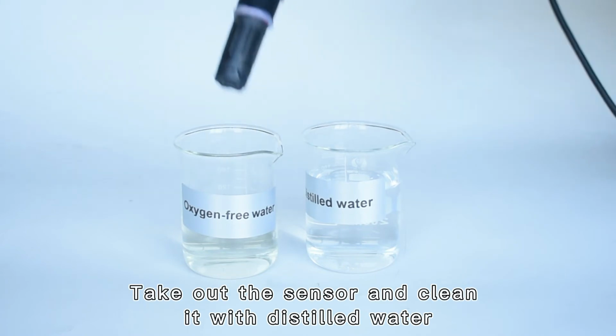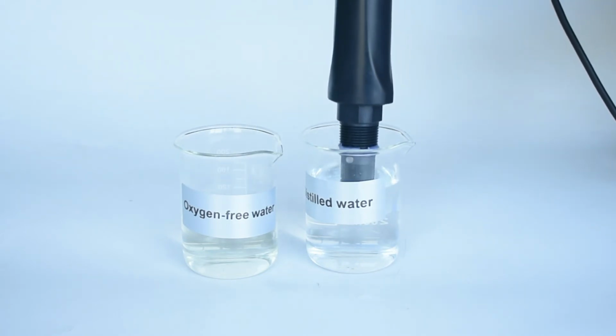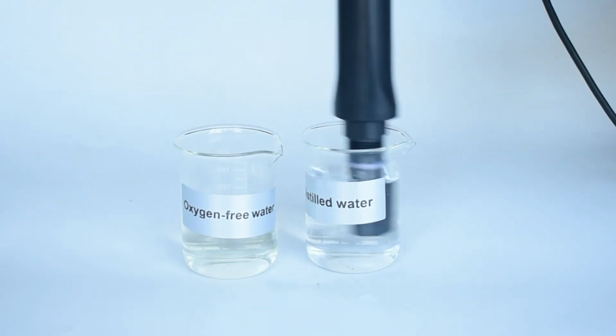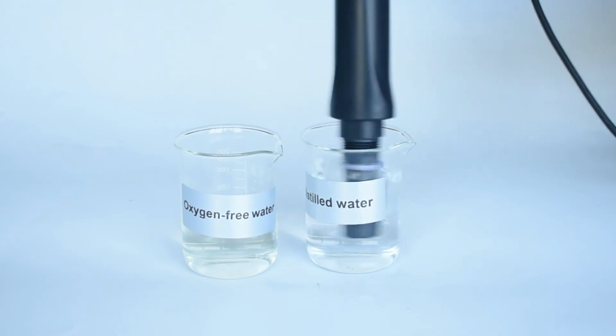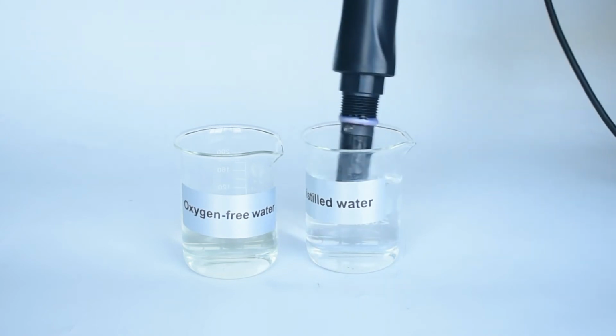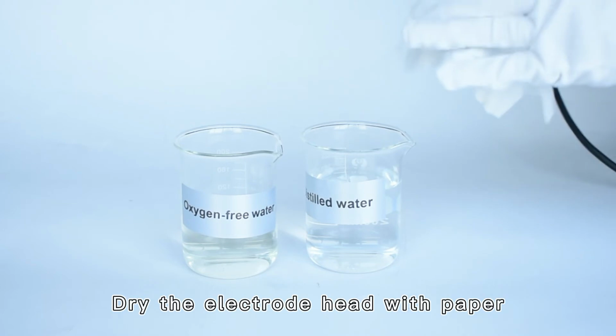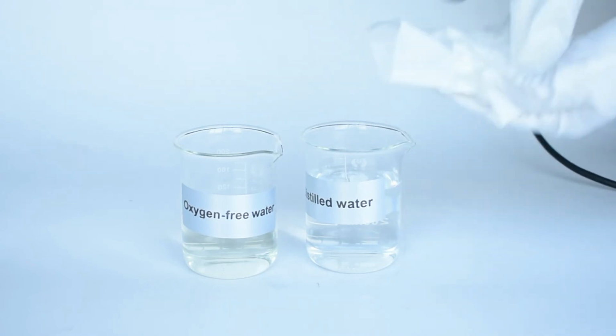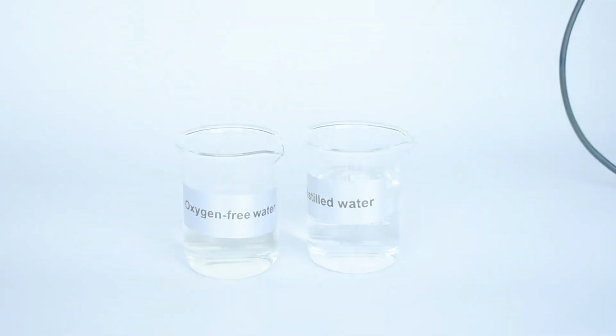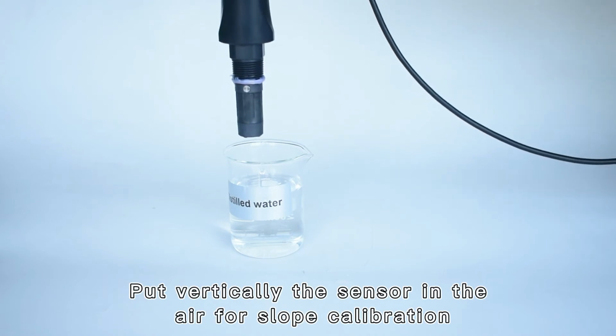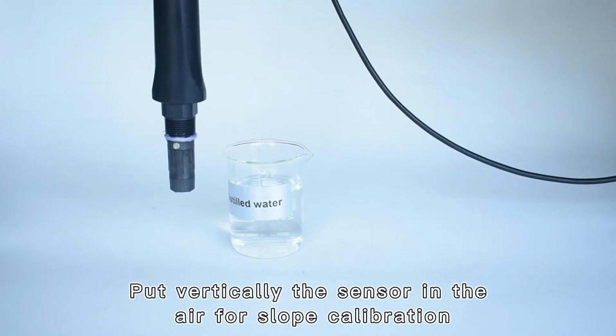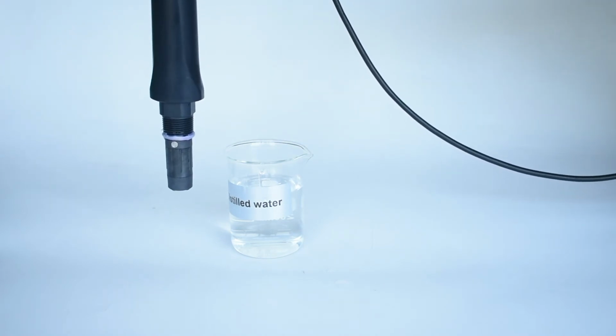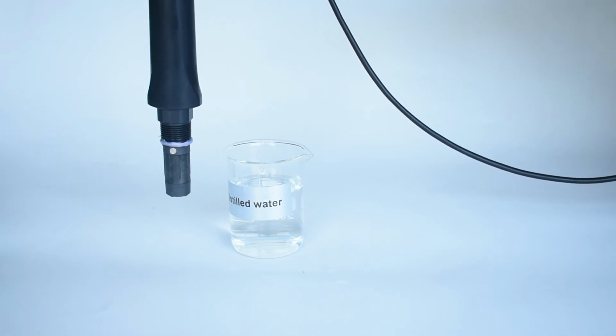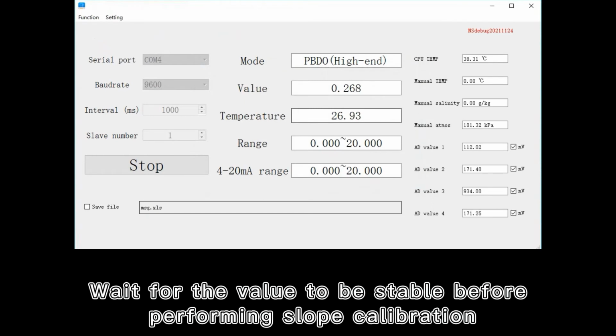Take out the sensor and clean it with distilled water. Dry the electrode head with paper. Put the sensor vertically in the air for slope calibration. Wait for the value to be stable before performing slope calibration.